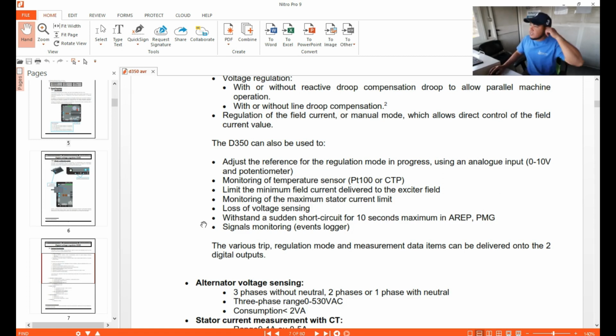Okay, so these are the only two connections where you can achieve this short circuit for 10 seconds. The rest of the connections, which are the standard connections only, like the shunt, are not capable of doing the short circuit.